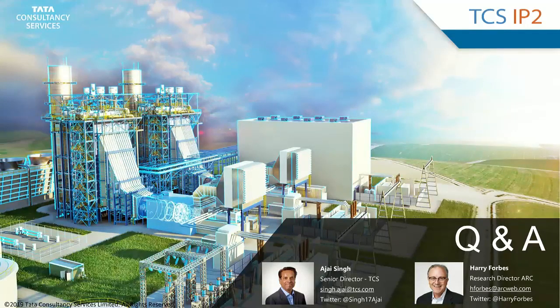Harry: The difference is whether a plant has to cycle on a daily or weekly basis, and this relates to the varying availability of renewables. A plant that becomes daily-cycling can go from 1 cycle per week to 5 cycles per week. Also, the volatility of wind or solar output can change quickly, adding cycles to a unit. So even small capacity factor utilization changes can have a big impact on unit cycling.